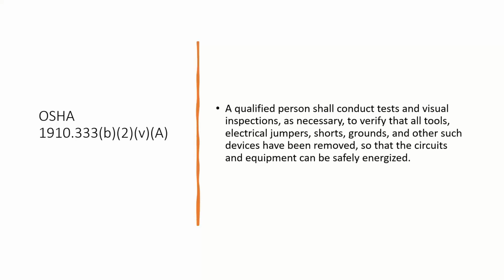One of the companies I worked for had a policy, and this was the best policy that I've seen anywhere. Anytime you put a ground on somewhere, you've got that breaker locked out on some sort of LOTO system. And anytime you add a ground anywhere, those ground cables get a lock put on the lock box, just like a person would. They essentially become a person. You hang a tag on the ground cables, you take the key for the lock that belongs to the ground cables and tie wrap it to the ground cables, and you hang a lock on that breaker or system of breakers. So there's no way it can be re-energized without getting that key off those ground cables, and hopefully reminding you that you've got them on there.